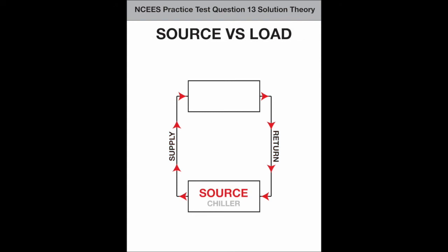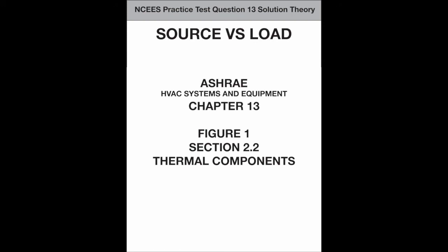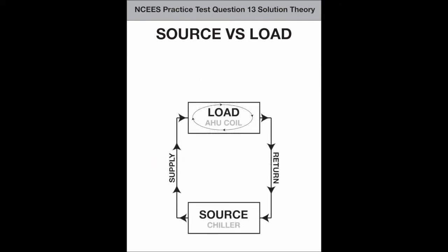The source is the device heating or cooling the flowing fluid, which is the chiller, and it is cooling in this case. The load is the device using the heated or cooled fluid to condition the space, which is the AHU in this case. Study up on this in ASHRAE HVAC Systems and Equipment, Chapter 13, Figure 1, and Section 2.2, Thermal Components. The supply comes from the chiller and goes to the AHU. The return comes from the AHU and goes to the chiller.